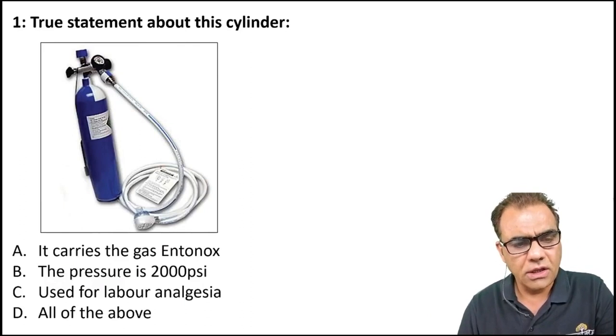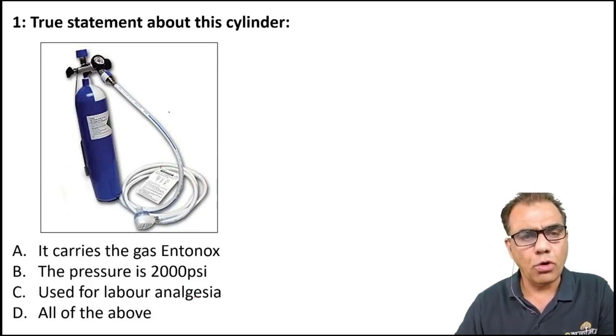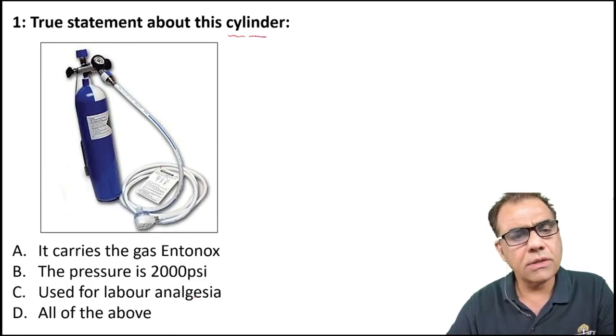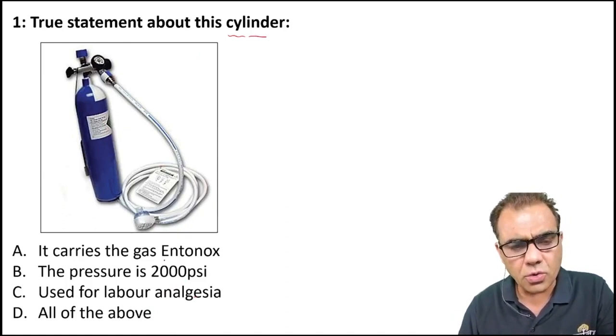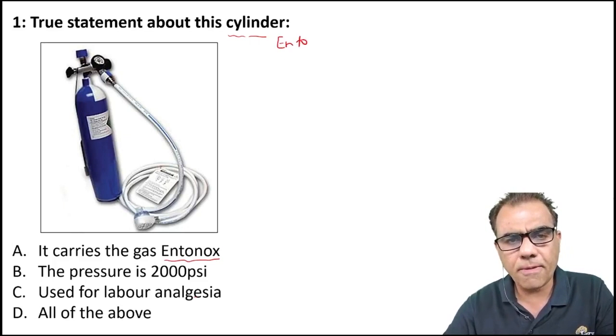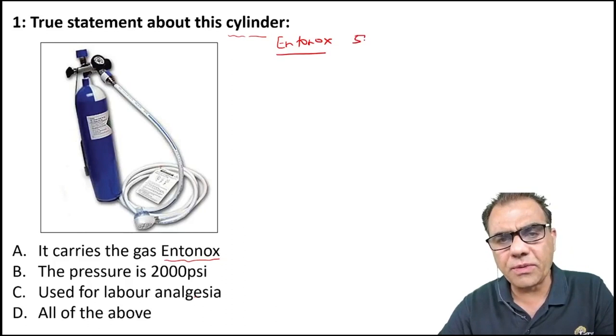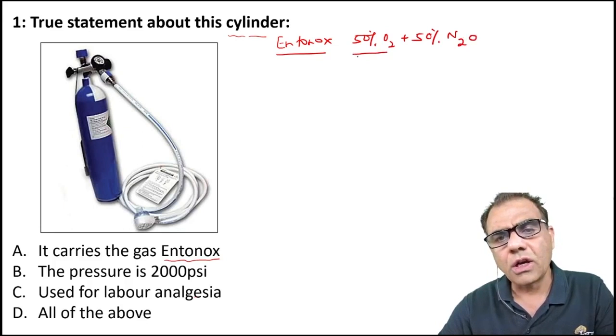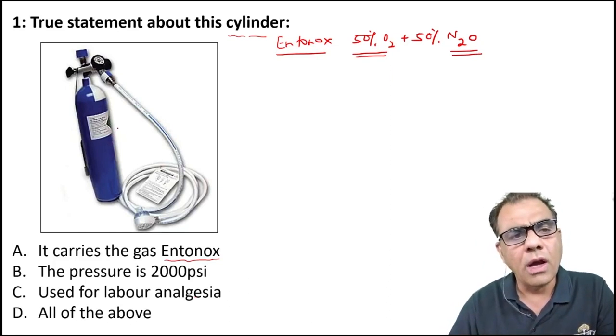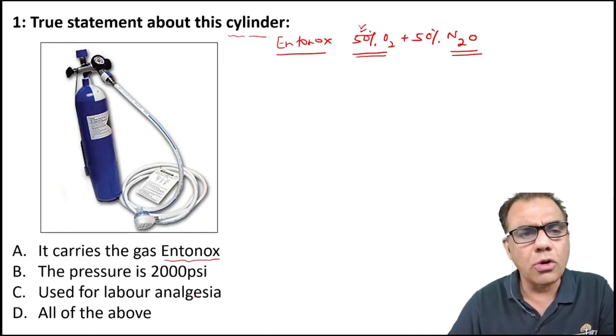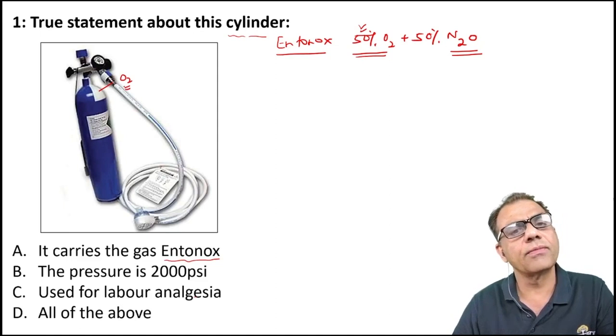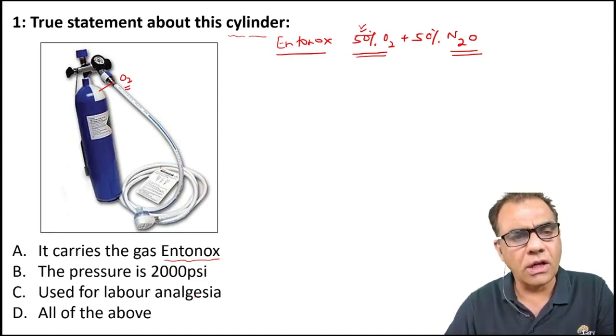It carries the gas Entonox. The pressure is 2000 psi, used for labor analgesia, all of the above. So this is Entonox, and Entonox is a mixture of 50% oxygen and 50% nitrous oxide. So the color of nitrous oxide cylinder is blue. So therefore the body of Entonox is also blue, and there is oxygen also. So this white quadrant indicates oxygen. So that is why the color of Entonox cylinder is blue body with blue and white quadrants.